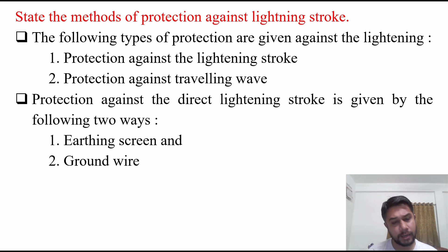Explain need of earthing screen protection against lightning stroke. So when a lightning strikes a substation or overhead line, a massive current is introduced. The earthing screen provides a low resistance path to ground, safely directing the lightning current away from sensitive equipment. Lightning induces overvoltages in electrical systems, and earthing screen helps dissipate the energy over a wider area and reduces the severity of surges.